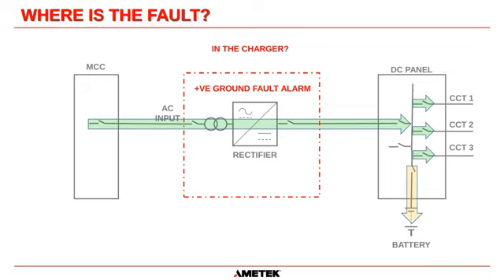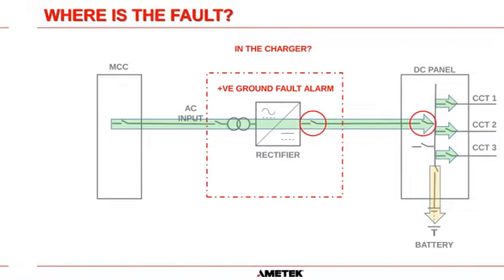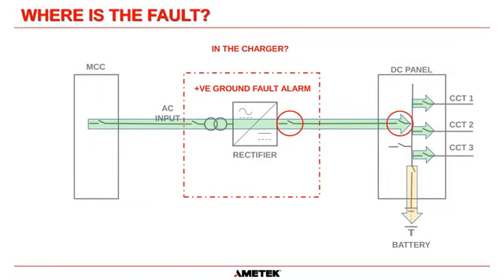And we should be able to do that without dropping any of your loads, unless the ground fault is on one of your load circuits, and I'll explain that in just a moment. So if we suspect that the ground fault is in the charger rectifier system, the first thing you should do is open the DC output breaker on the rectifier charger. Basically, we are disconnecting the charger from the DC panel and the battery.